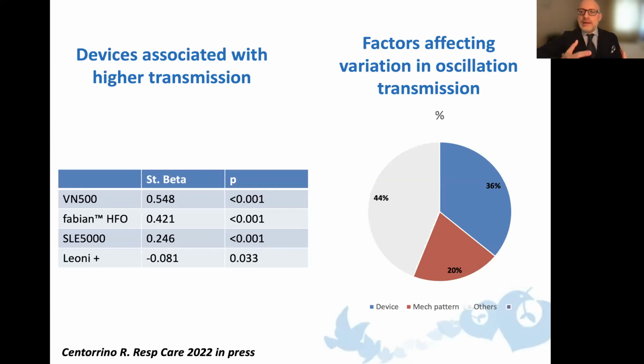a multivariate regression model, so let's say a multivariable regression, in order to understand what are the factors that are more significantly and more importantly influencing our outcome, which is the oscillation delivery. You will see the two ventilators with the best oscillation delivery, so the higher oscillation transmission, are again, as I told you, the Fabian and the VN500, but also that the type of device accounts for 36% of oscillation delivery. So it means that if you choose the right device, you have more than 1/3 of the, let's say, possibility to have a higher oscillation delivery.